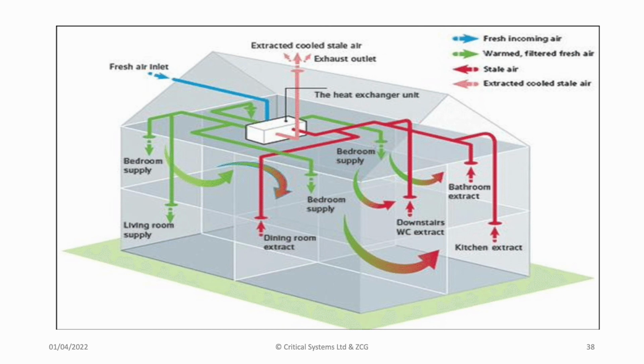So there will be an air handling unit, probably in the loft, which draws in fresh air, and it exchanges the heat with the exhausted air from the parts of the property where hot air, moist air, or odours are likely to exist. And we supply the reheated, the heat recovered air back to main occupied parts of the property. There is clearly a need to have ventilation ductwork in the property, and this may be a physical constraint in existing buildings.